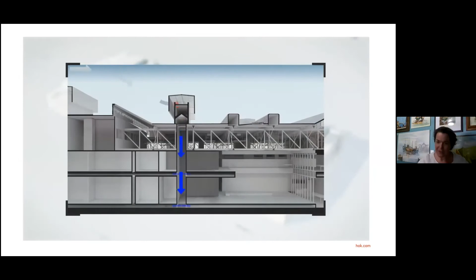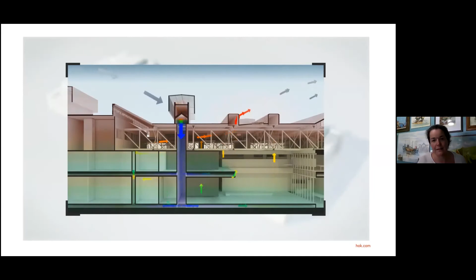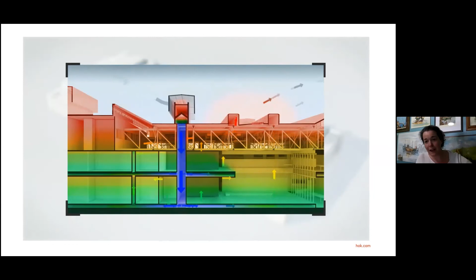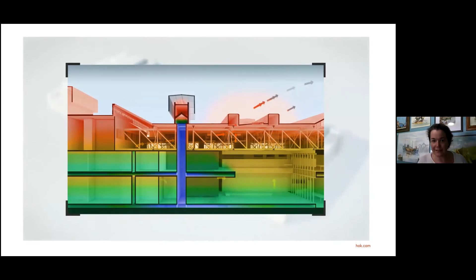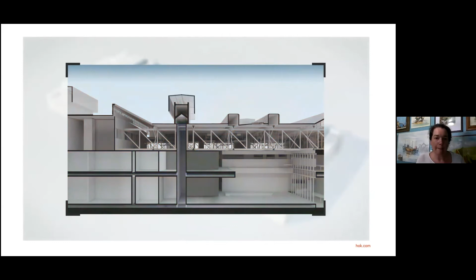As cool air wants to do, it drops, and we were able to distribute it through an underfloor air distribution system. That eliminated all the cooling towers and just about all the fans, though we did add a pump for that deep sea well. And as hot air rises, we were able to exhaust the building fairly passively as well. We had to do a lot of CFD analysis to make sure everyone would get adequate outside air and be thermally comfortable.